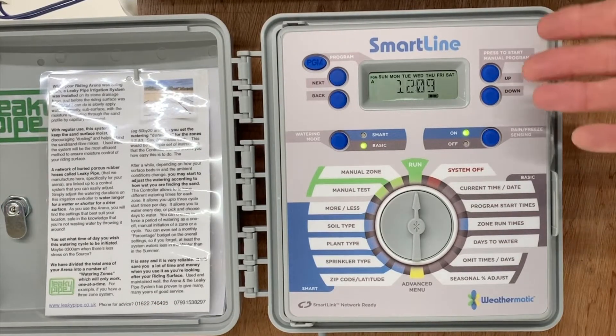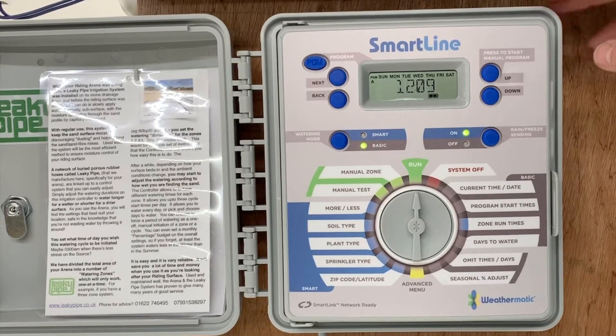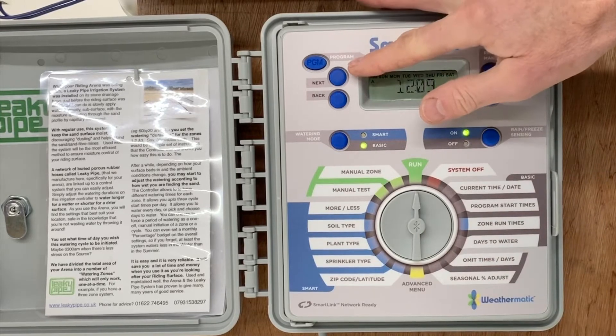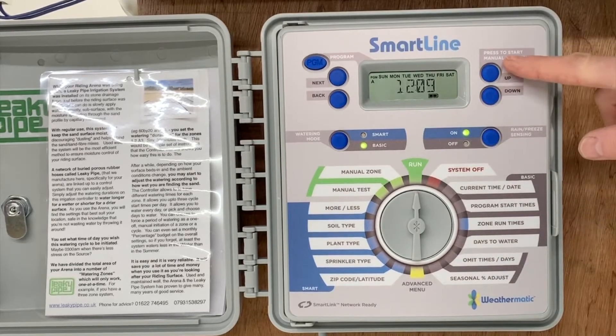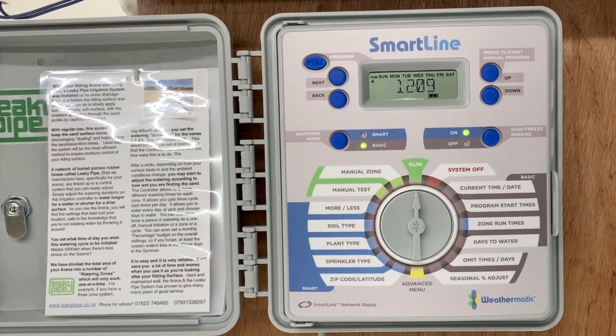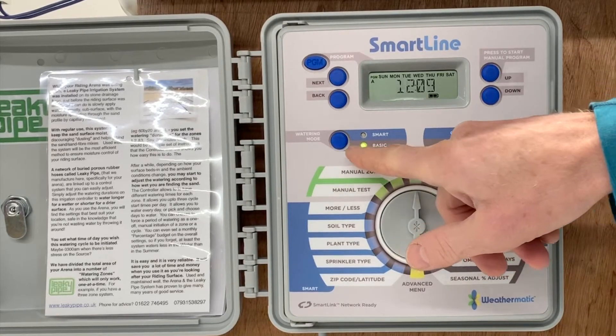On the right-hand side, you can see the blue and grey panel where the programming of the watering is done. The grey selection dial in the centre of the panel is normally set to run — this is the day-to-day position. The blue buttons at the top left are for selection and the ones on the right are for adjustment of the values shown on the display in the centre. Unless you have specific instructions from us, the mode switch should be set at basic for riding arena watering.